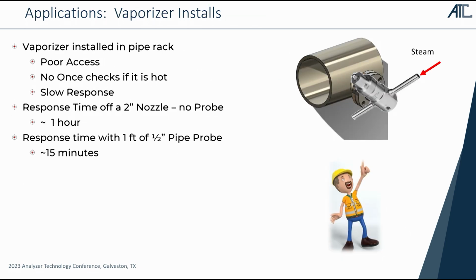So one of the great applications for this is things like vaporizers. We see a lot of vaporizing regulators get installed in the petrochemical facility, and you'll go into a plant, you'll be walking along, and there's a vaporizer, and it's somewhere up there in the pipe rack. And you go, how do you guys maintain that? Oh, we don't. We never go up there. How do you know it's hot? We don't. We run steam to it. How's your steam traps? I don't know. I haven't checked. Steam is one of two temperatures. It is really, really, really hot, or it's cold. Depends on how your steam traps are.